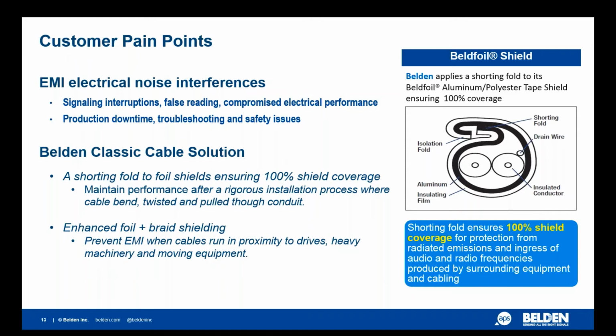It also has an enhanced foil and braiding, which prevent EMI when cables run in proximity to drives, heavy machinery and moving equipment. So if you look to the side there on the right hand side, if you screen, you'll see that the fold actually goes up and then folds back on itself for the actual shield foil. This actually helps protect the cable, as we've just explained, on the EMI characteristics. The other manufacturers just wrap the foil, they don't do the shorting fold.